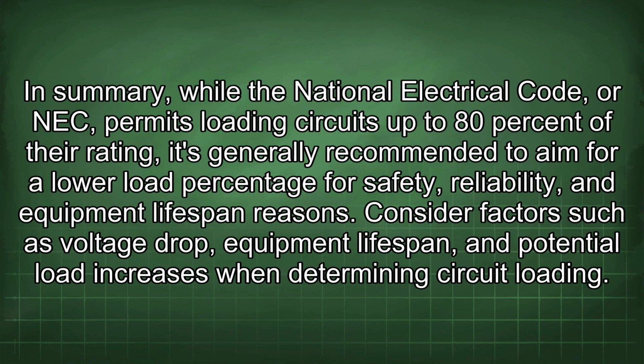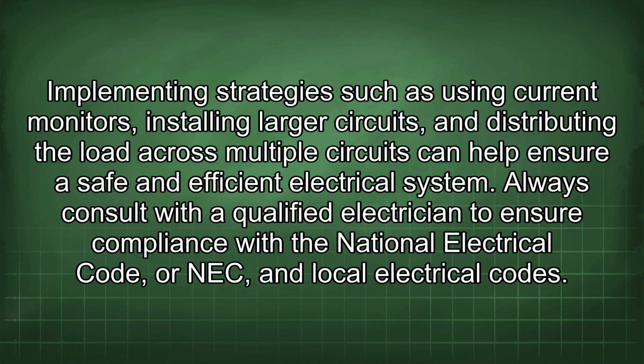In summary, while the National Electrical Code, or NEC, permits loading circuits up to 80% of their rating, it's generally recommended to aim for a lower load percentage for safety, reliability, and equipment lifespan reasons. Consider factors such as voltage drop, equipment lifespan, and potential load increases when determining circuit loading. Implementing strategies such as using current monitors, installing larger circuits, and distributing the load across multiple circuits can help ensure a safe and efficient electrical system.